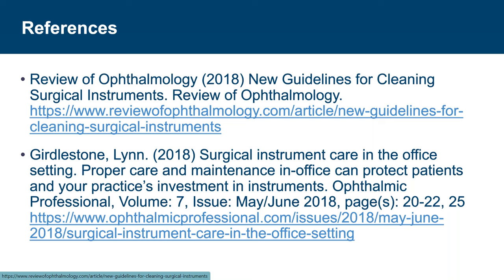Question: 'Are there specific types of instruments more prone to causing TASS?' Instruments with narrow lumens or complex designs are more prone to inadequate cleaning, which can retain debris or chemicals that lead to TASS. Such instruments require meticulous cleaning with specialized brushes or tools and should be flushed thoroughly to ensure all residues are removed. Enhanced inspection and testing of these instruments may also be necessary. In the event of a suspected TASS outbreak, immediate actions include halting the use of all suspect instruments, reviewing and documenting reprocessing steps, and conducting a thorough investigation of the surgical environment and processes. Samples from instruments and surgical solutions should be taken for analysis to identify the source of contamination, and relevant personnel should be notified.